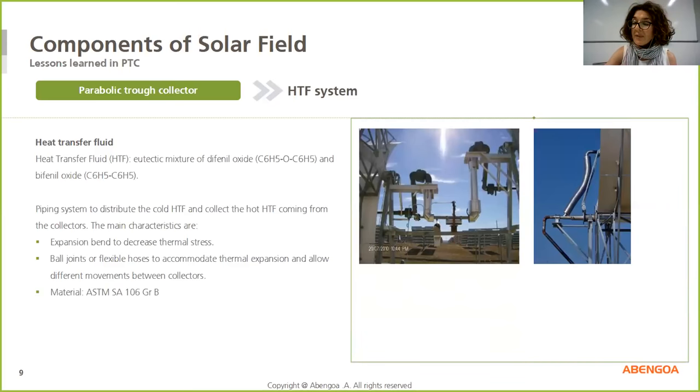During the life of the plant, a degradation percentage is considered. The degradation produces high boiler and low boiler components as the main result. And the by-product concentration has an operational limit based on the HTF supplier's requirements. The latest recommendation is 5% in low boiler and 20% in high boiler.